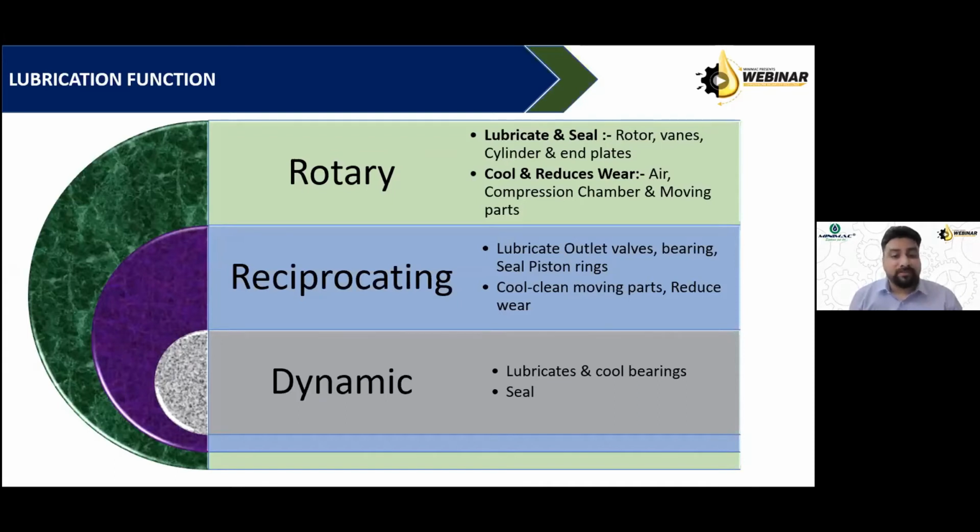the rotary compressors. In case of reciprocating compressors, there are piston rings which do separate the lubricating oil from the entrant gases. But there is a possibility of leakages. Whenever these piston rings get certain wear and tear, there is a possibility that the compression chamber gases would come down into the lubricating chamber. And this is a normal practice which does happen.